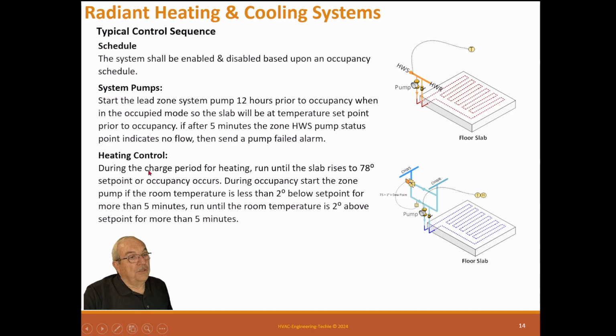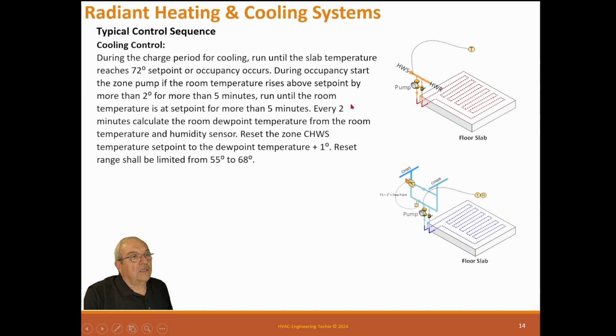Heating control. During the charge period for heating, run until the slab raises to the 78 degrees set point or occupancy occurs. During occupancy, start the zone pump if the room temperature is more than 2 degrees below set point for more than 5 minutes. Run until the room temperature is 2 degrees above set point for more than 5 minutes. So heating is pretty simple. We try to charge it ahead of time, and then if it gets cold during operation, we turn it back on. No big deal. Cooling control.